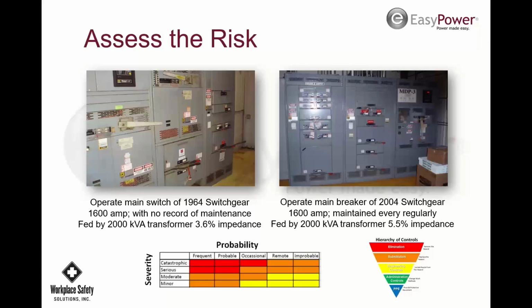But sometimes you have controllers, control cabinets and things like that. They're usually pretty low level, unless they're significant size cabinets fed by a 400 amp breaker. But generally they're pretty low. But some companies want them labeled as well, so it's up to the company.